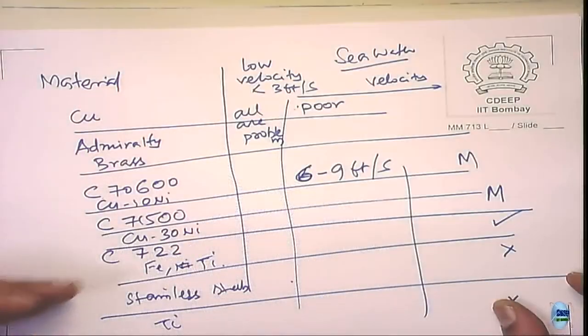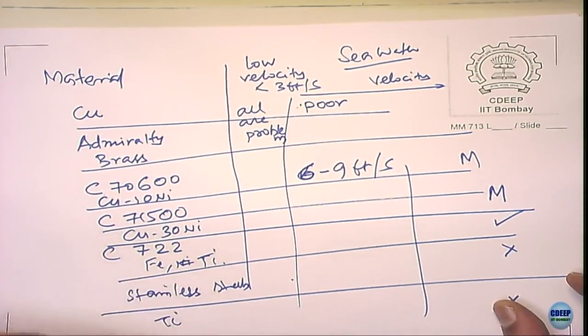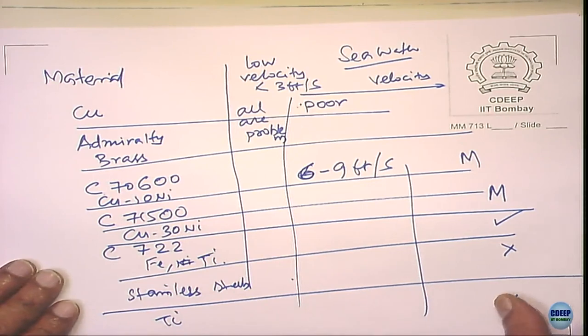Now, if you look at the copper based alloys compared to the stainless steel, stainless steel is much harder, and copper based alloys are reasonably softer. So the utility of these materials are restricted based on the flow rate applications. If the flow rate is increasing, I think the choices are going to be much more limited. You go for stainless steel or titanium based alloys.